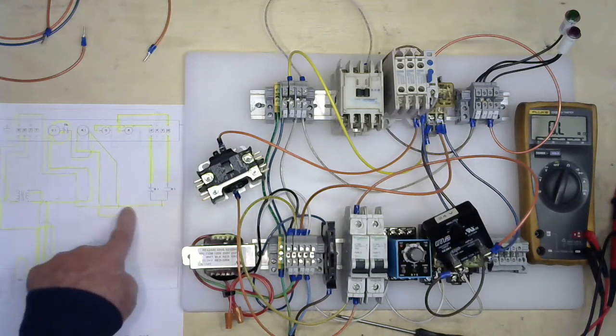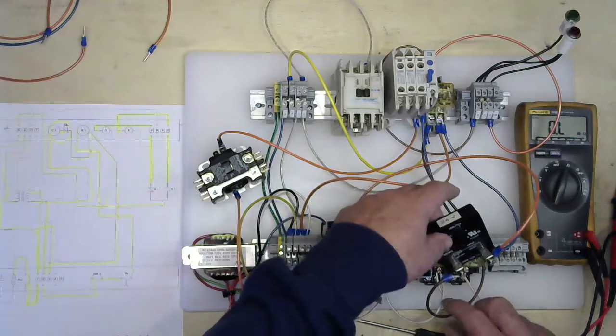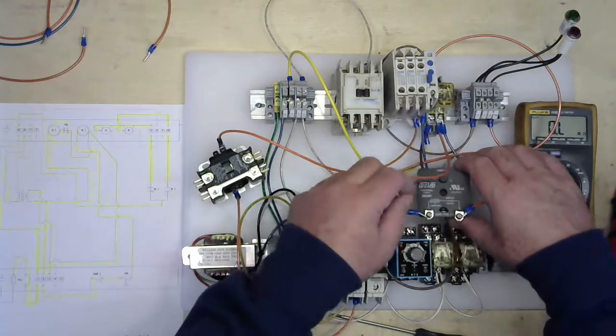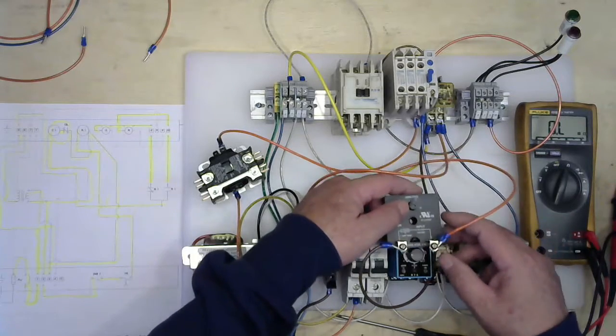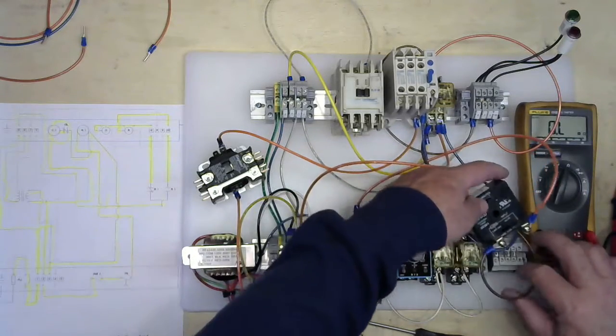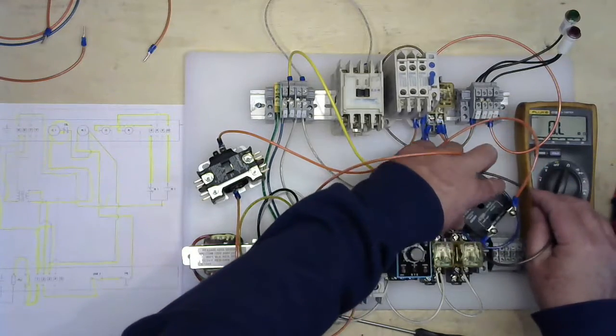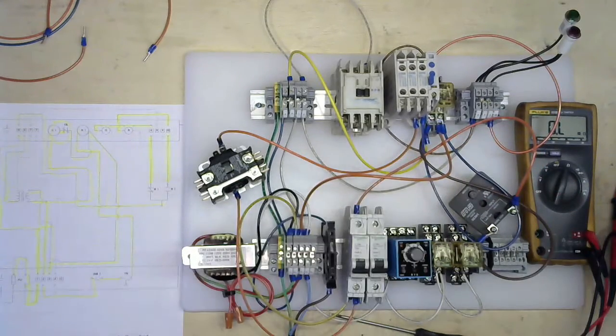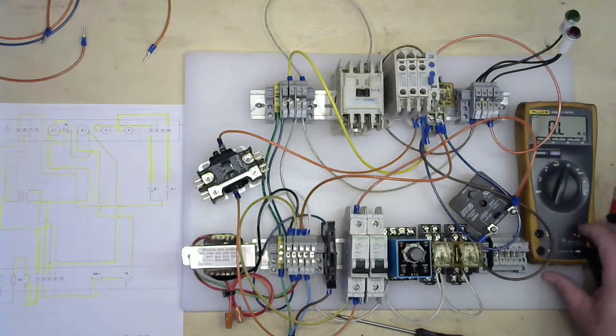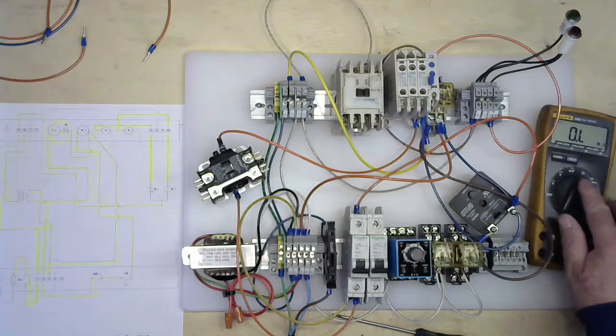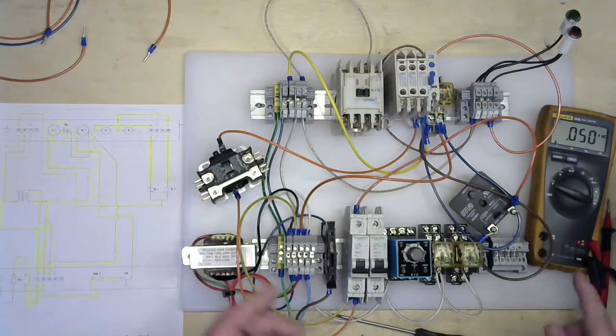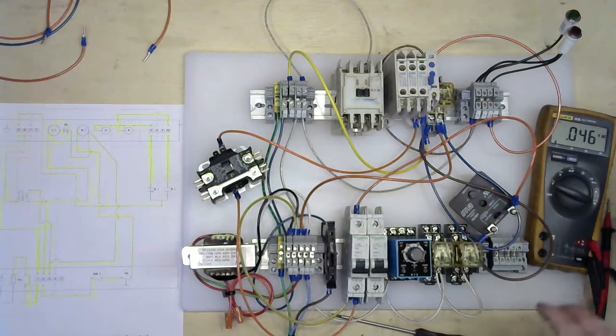Since you've highlighted the wiring as you went along, and you have your loose wiring here, as you can see, it just kind of wants to float, per se. You try to find a spot for this to settle down so we can adjust it as necessary. So everything should be connected already. Our meter's set on ohms. Before I do anything, I like to put my meter on voltage so that I'm not quickly checking something while it's on resistance and possibly have a fuse go bad. Now all I have to do is power up the trainer, and we'll see what happens.